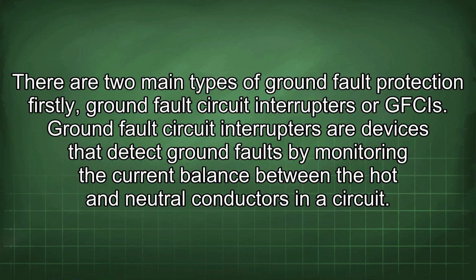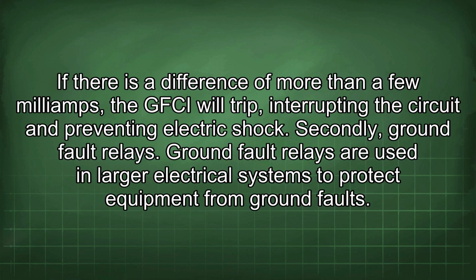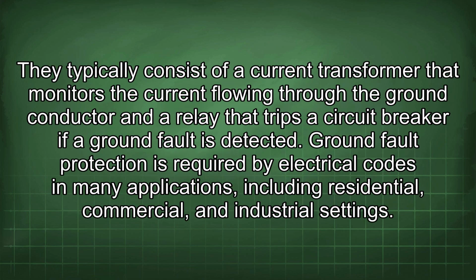There are two main types of ground fault protection. Firstly, ground fault circuit interrupters, or GFCIs. Ground fault circuit interrupters are devices that detect ground faults by monitoring the current balance between the hot and neutral conductors in a circuit. If there is a difference of more than a few milliamps, the GFCI will trip, interrupting the circuit and preventing electric shock. Secondly, ground fault relays. Ground fault relays are used in larger electrical systems to protect equipment from ground faults. They typically consist of a current transformer that monitors the current flowing through the ground conductor and a relay that trips a circuit breaker if a ground fault is detected.